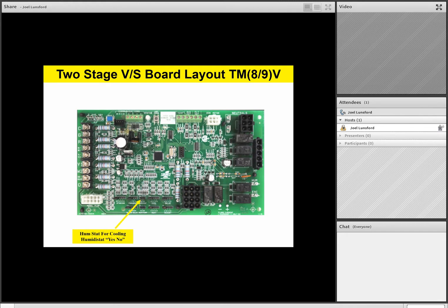So be sure, if you're not going to use that cooling dehume terminal that we talked about earlier on our low voltage wiring, make sure that that humidistat jumper is in the no position. No position is normal if you're not going to use that dehume terminal. That's very, very important, because we can affect our cooling airflow if that jumper is not in the right position. So factory setting is no, and we recommend you double check that during install to make sure it's in the no position if you are not going to use the dehume terminal.